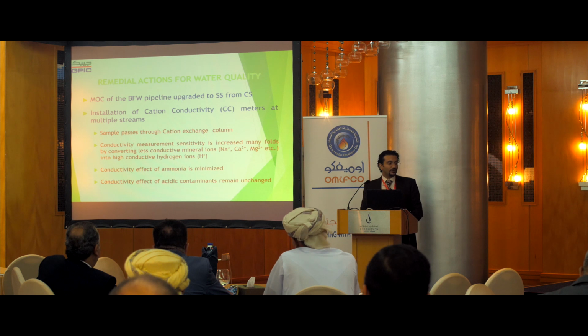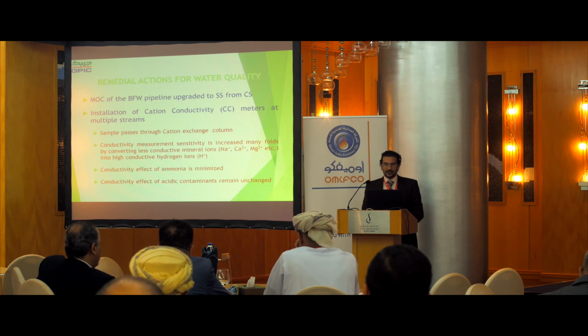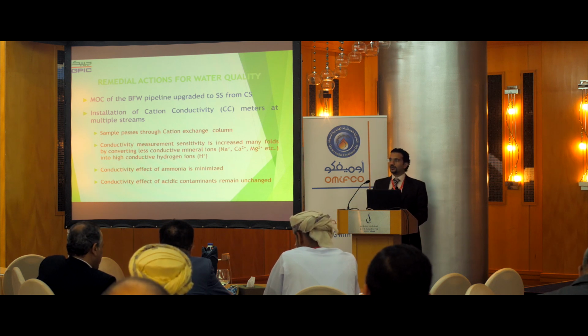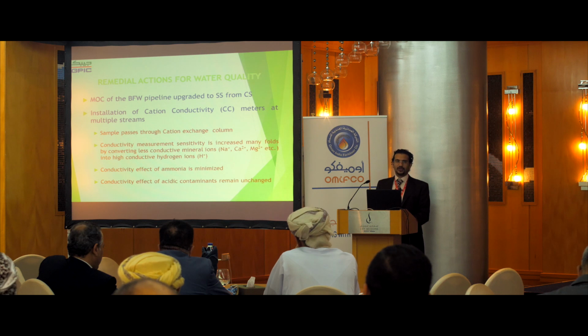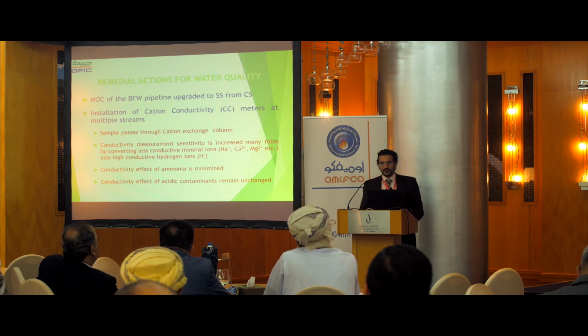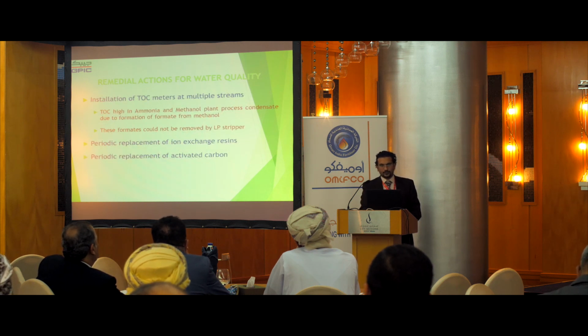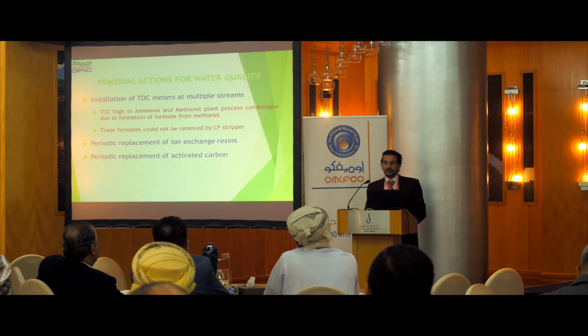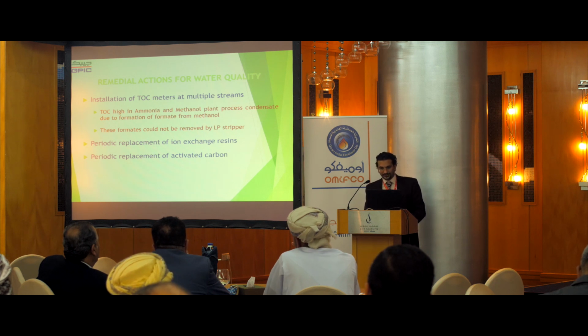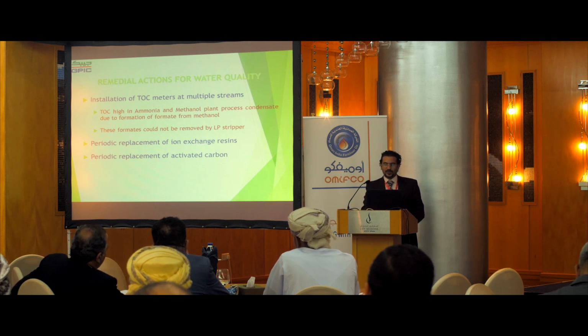For the water quality, the boiler feed water pipeline was upgraded to stainless steel from carbon steel. And we installed cation conductivity meters in multiple streams to closely monitor the conductivity and the pH of the water and the steam. Installation also of total organic compound meters at multiple streams. It was high in ammonia and methanol plant process condensate due to the formation of formate from methanol, and it could not be removed by the LP stripper and the utilities plant.